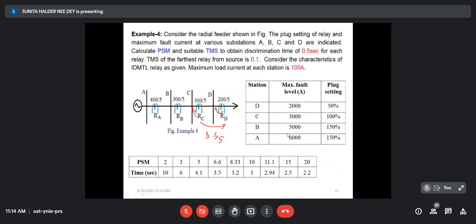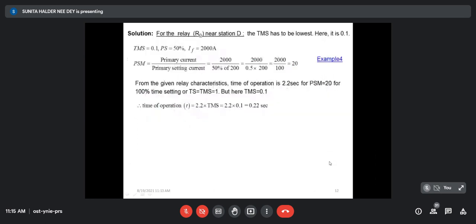The fault level is far higher than 100 ampere. We shall start from the far end point from the source — that means from station D. At station D, maximum fault current is 2000 ampere. Plug setting is 50%, so from there we can calculate the plug setting multiplier. The CT ratio is 200/5, so if we calculate from the primary side, the relay will start to operate for 100 ampere current on the CT primary. Fault level is 2000 ampere, so the plug setting multiplier is 2000 divided by 50% of 200, which equals 20.